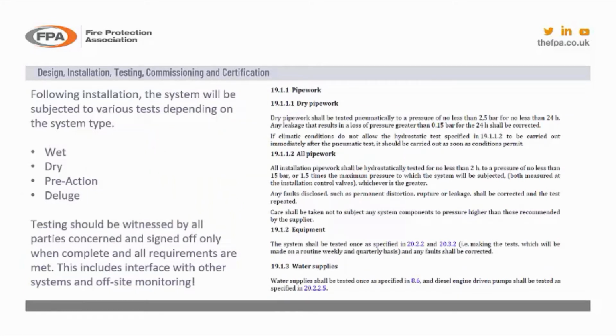So moving on to testing. On completion of the installation, or sections such as the floor or shop unit, if you were to zone it, you can sectionalize test it, or you can test the whole system in its entirety. That depends on the contract, the type of building, how it's programmed to work, and how it's handed over in various sections. The system should be subject to a full test regime, and as you can see on the right hand side, there are different requirements for different types of system. You've got wet, dry, pre-action and deluge systems. Each system has a different type of requirement.